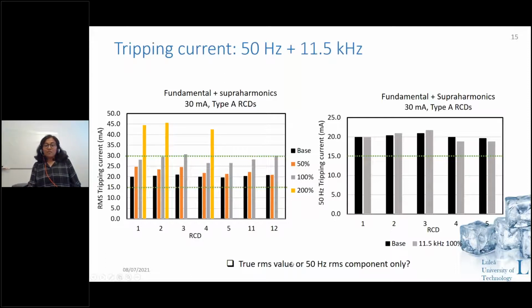They tripped accordingly. So in the standard, they mention RMS value, but when we had meetings with several RCD manufacturers, they all consider that only the 50 hertz component has to be considered in the tripping current. So there is a need to clarify which frequency components are to be considered in the leakage current, or what should be the constitution of the leakage current that should be counted as 15 milliamperes, whether it should be the overall RMS value or just the 50 hertz component. But going further, we considered the 50 hertz component because that is what all the RCD manufacturers told us. So for now, we will be comparing the results with the 50 hertz component. But I think this is a clarification that is needed.